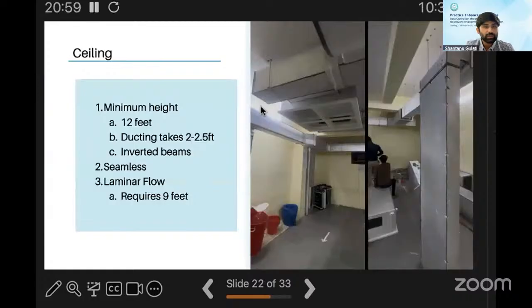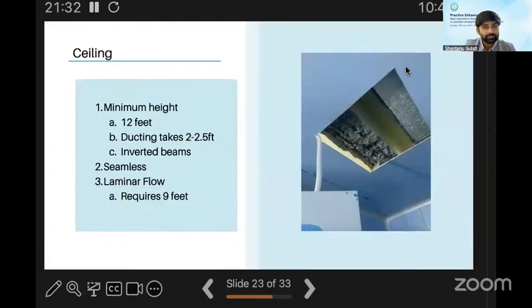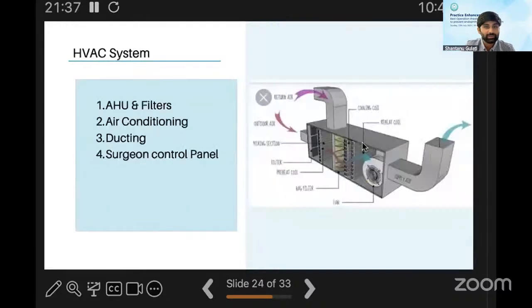A very practical point here is about the height of the operation theatre. You have to provide your vendor with a minimum height of 12 feet. We did not have that here, as you can see, because of the beams, which is why our ducting came below the 9 feet level. This is not recommended because for the flow to be laminar, the height of the laminar plenum has to be at least 9 feet from the floor. And this also affects the seamlessness. To prevent that, you can either plan to not have a beam in the area where you're planning the OT, or you can have inverted beams that are present on the roof and not inside. This is just an image that we had to cut the beam here to fit the OT ceiling.